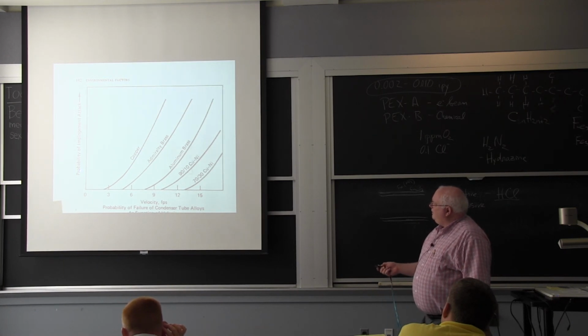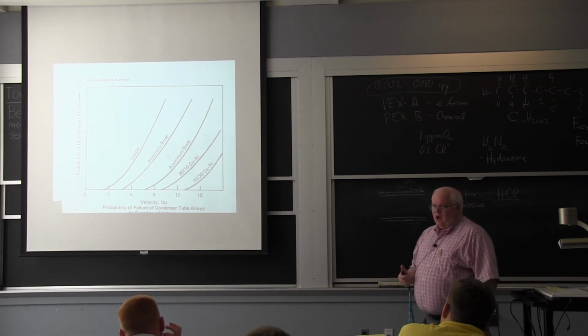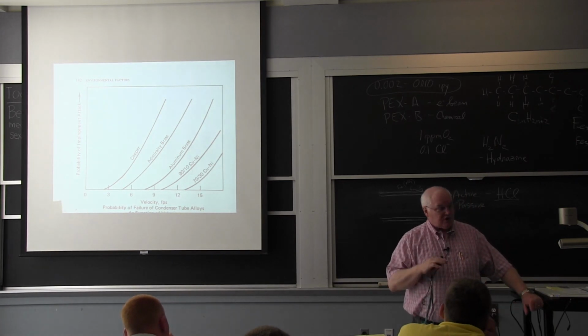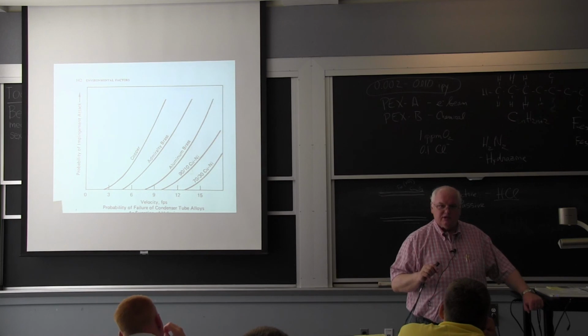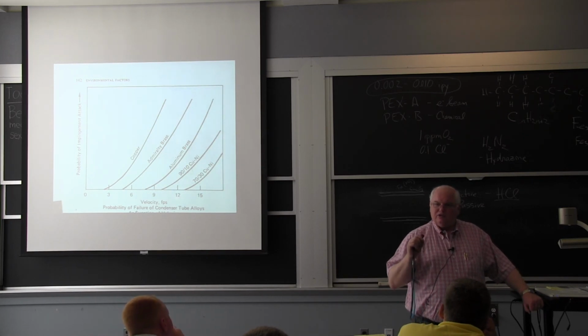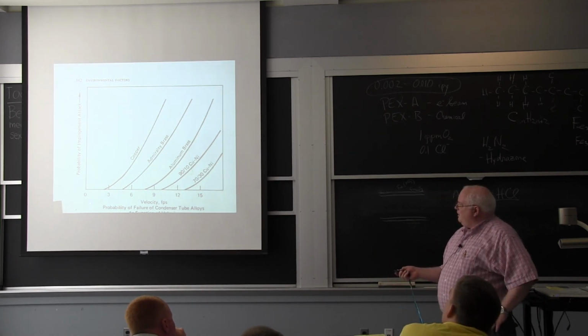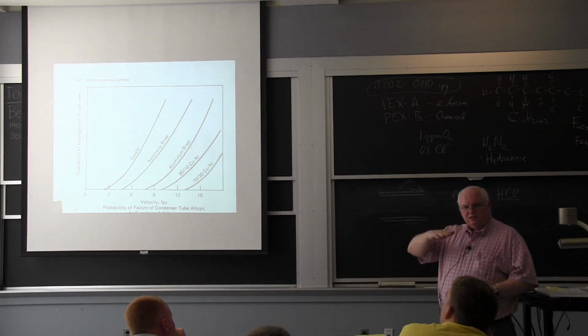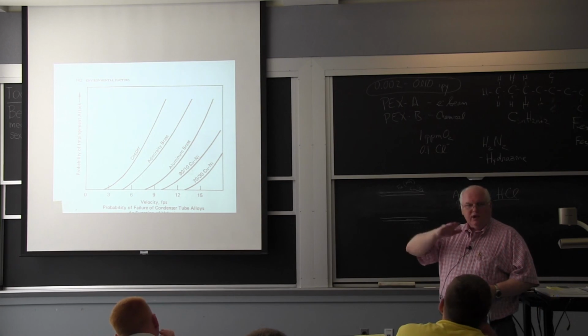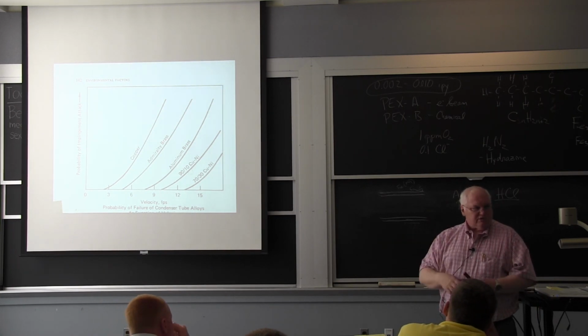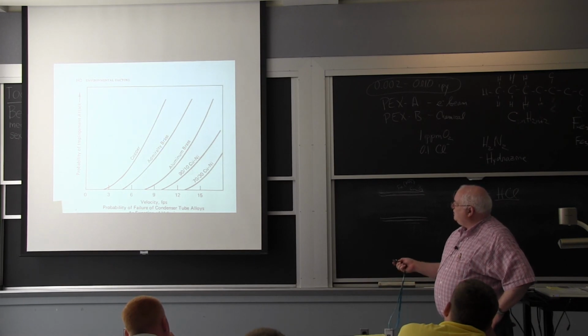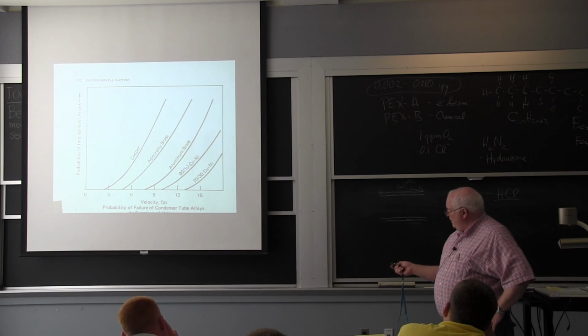Anyway, the probability of attack versus velocity in feet per second on copper: copper's got a fairly soft but protective oxide, just like protective films on other things. But all water has some total dissolved solids - microscopic solids - and at certain velocities those solids erode away that oxide skin abrasively. If you use Admiralty brass, you can tolerate considerably higher velocities. Aluminum brass forms a very tenacious aluminum oxide skin. If you want something even better, you go to cupronickel alloy.